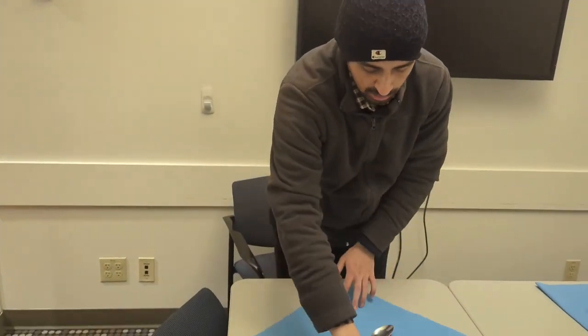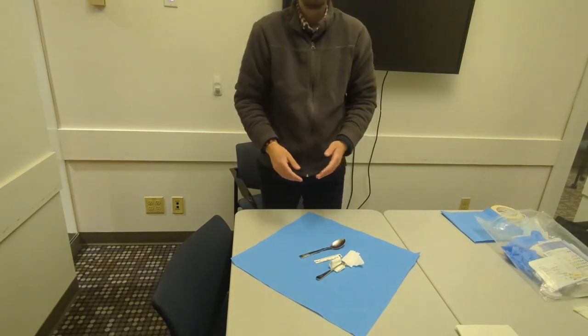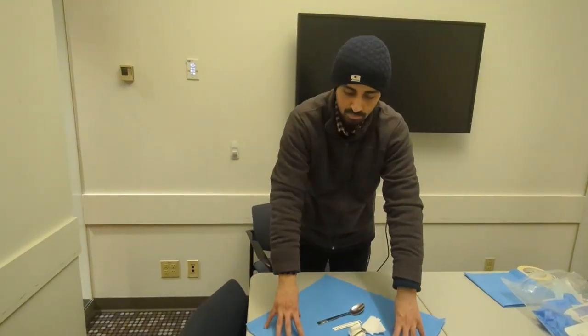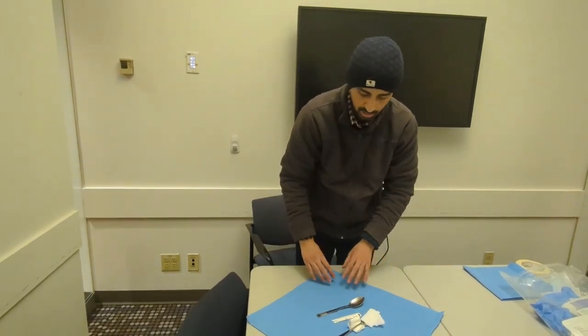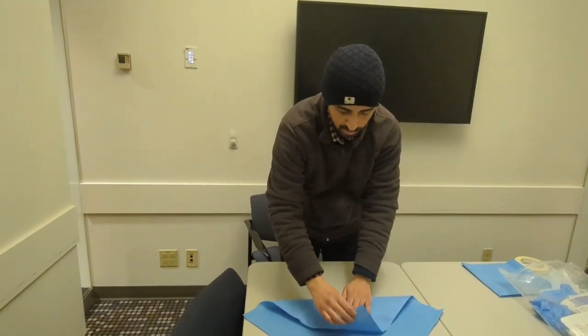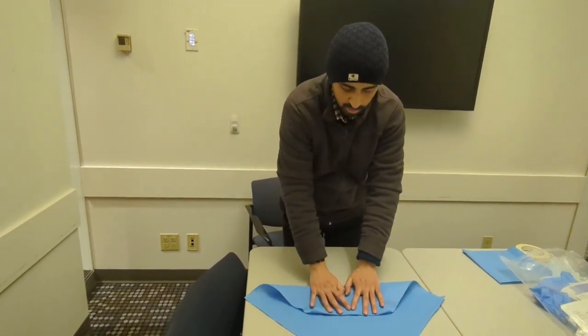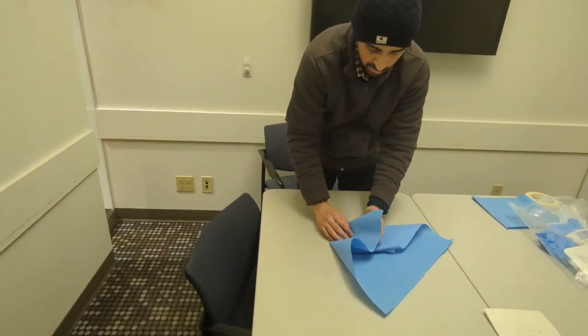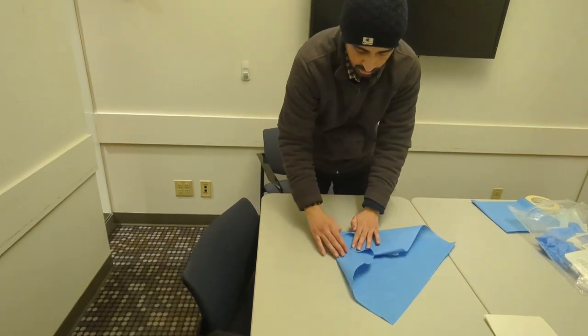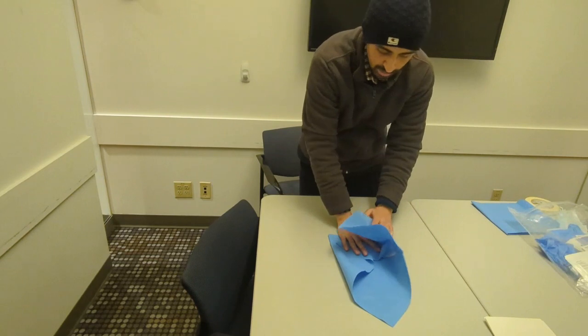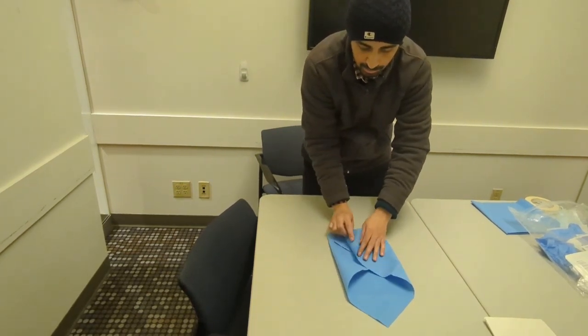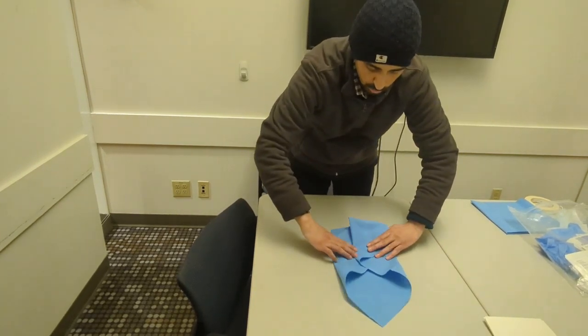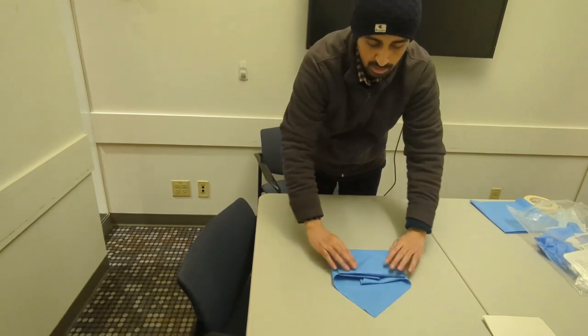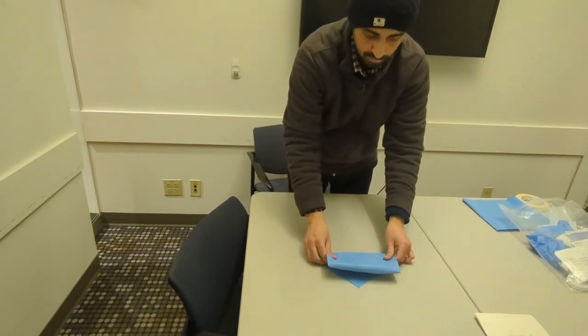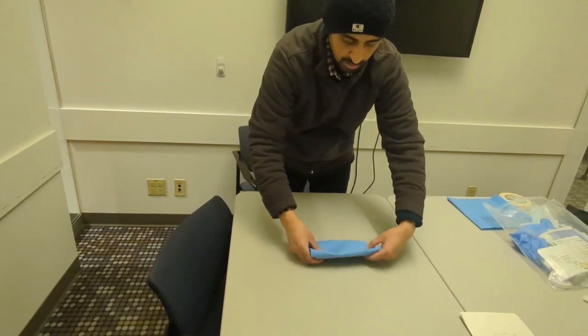After we have done that, we are going to start wrapping our instrument. We have our sheet here that we are going to use to wrap the instruments. We take one end of our sheet and fold it by pulling the end back, and similarly we fold the other end as well, pulling the extreme end of the sheet back. The rationale is that once we are done with sterilization, it will prevent any recontamination that could occur when we open the wrap of the instruments. This is how we completely wrap our instruments.